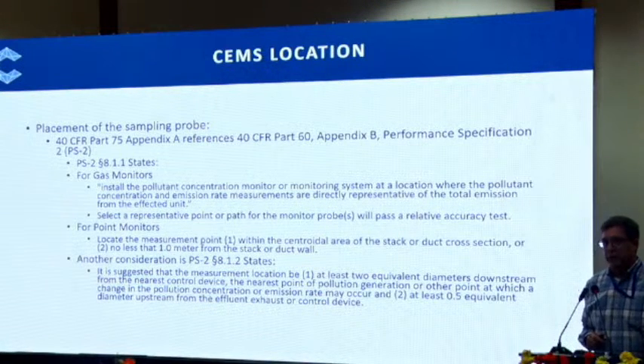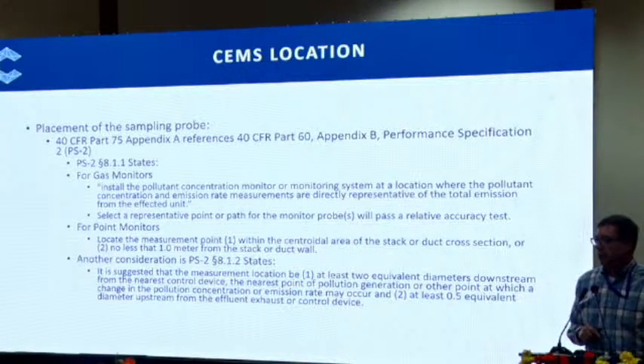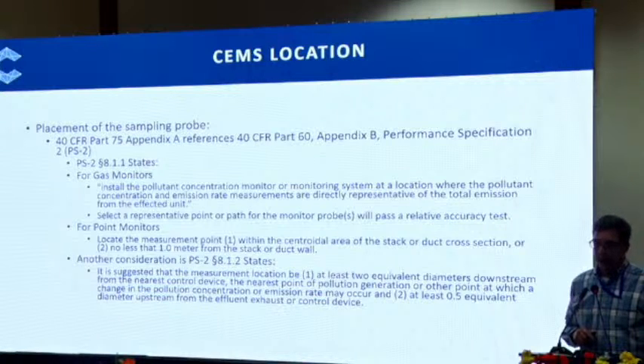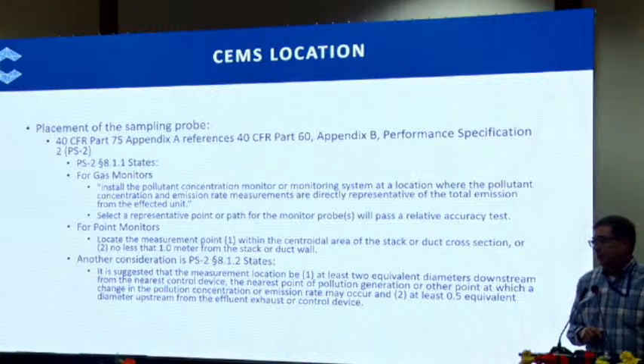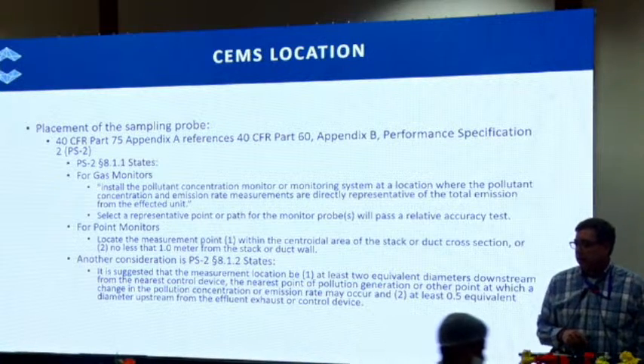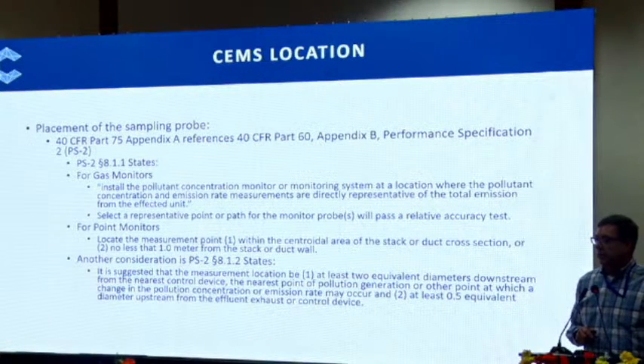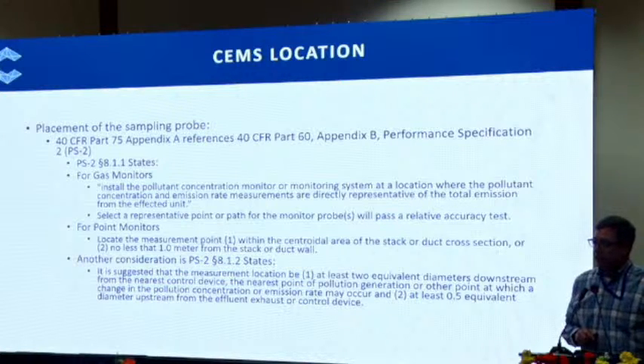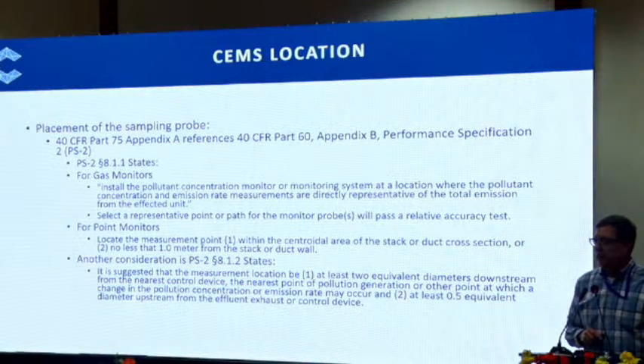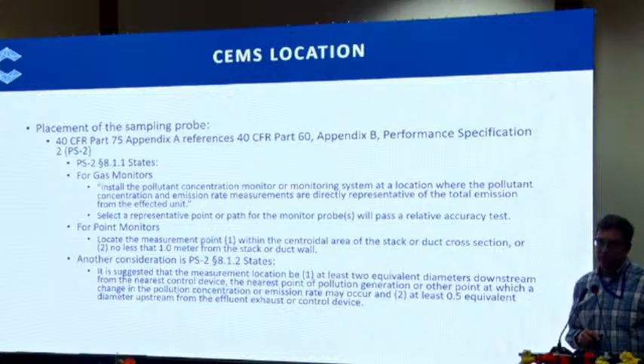For point monitors or in situ, locate the measurement point within the centroidal area of the stack or duct cross section, or no less than 1 meter from the stack or duct wall. Another consideration: it is suggested that the measurement location be at least 2 equivalent diameters downstream from the nearest control device, the nearest point of pollution generation, or other point at which a change in the pollution concentration or emissions rate may occur, and at least 0.5 equivalent diameters upstream from the effluent or exhaust of the control device.